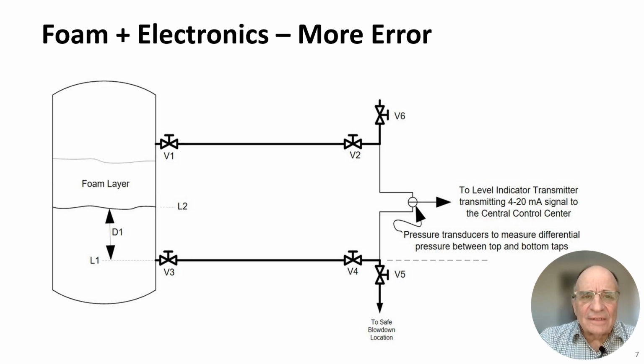So adding electronics did help us with communicating to the control room, but it may have added even more errors to our actual reading. If you add foam on top of that, you even increase the errors more. So now what we have is a foam layer that's causing an error, plus the potential for a personnel error in calibrating this sensor that could add error, and now that information is sent to the control room, and the control room operator is making judgment calls based on information that could be flawed.